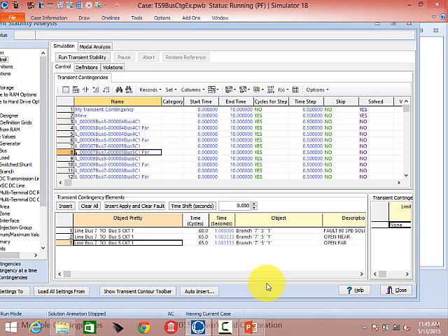So when you're talking about multiple contingencies in this, these are single contingencies, not simultaneous contingencies. Correct. They are single. They're applied sequentially. So we apply one, then we go back to our starting case, apply another. They're not like cascading or sequential or anything like that. What do you mean by sequential? Because each contingency can have multiple operations in it. Right, so the fault and the load, you can have multiple operations.